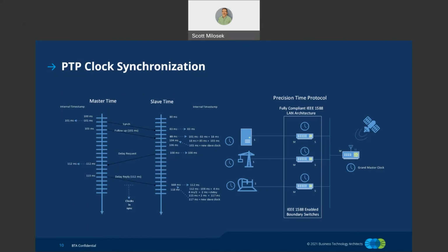Given the switches save the received data packets completely and the queue effects can be considerably long, under certain circumstances great fluctuations can occur here. At low network load, this may have little effect, but during times of greater network load, this can definitely affect time synchronization. And this is resolved using Ethernet switches that are IEEE 1588 PTP boundary clocks.